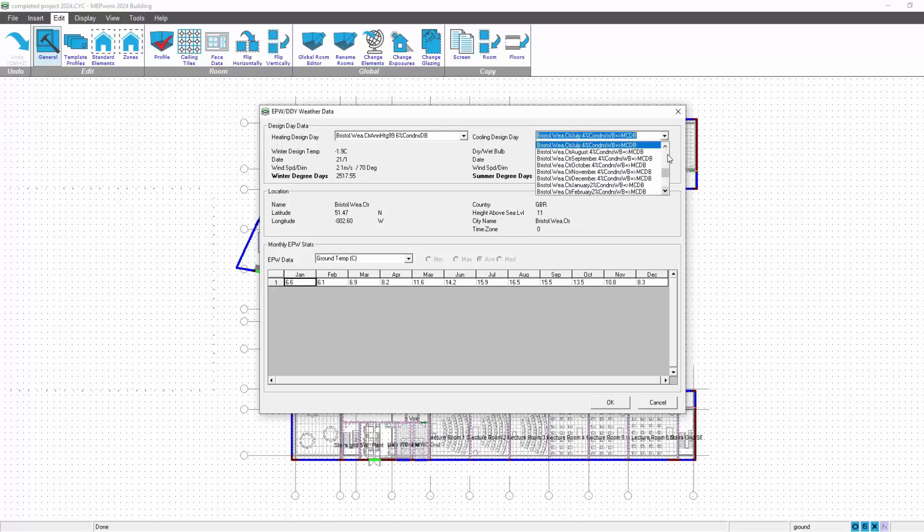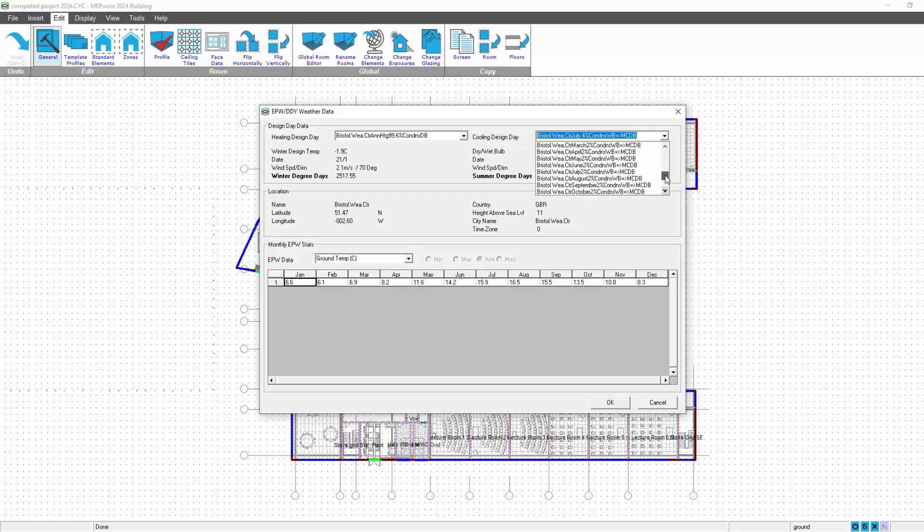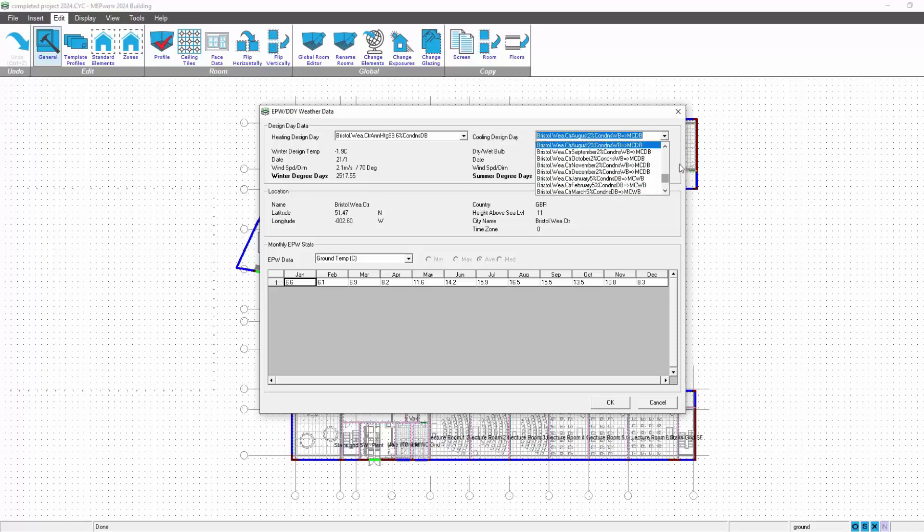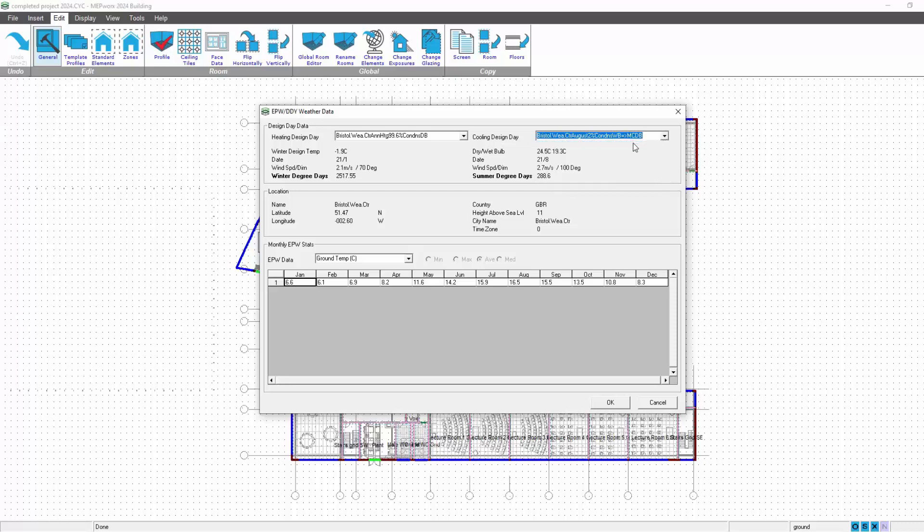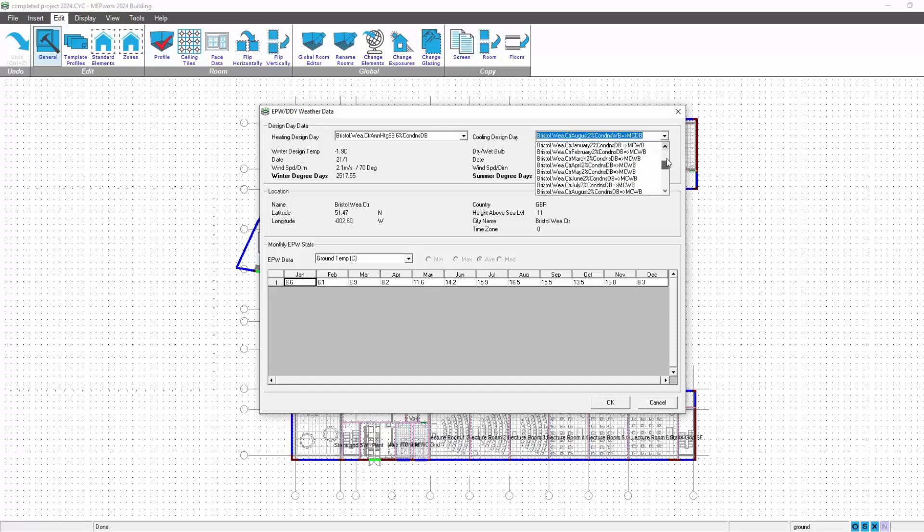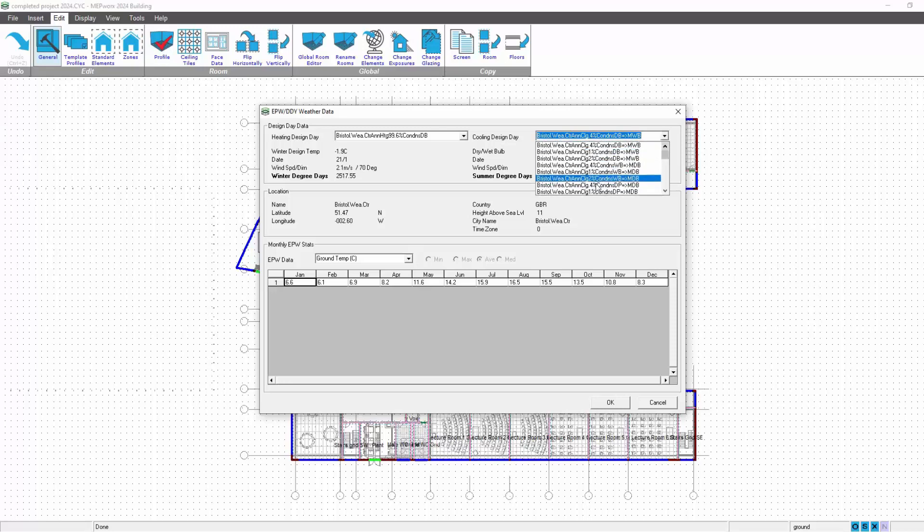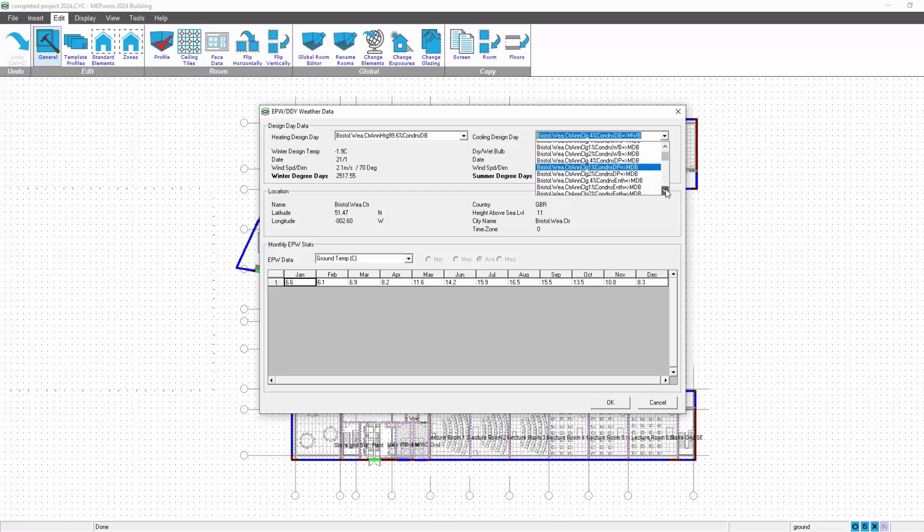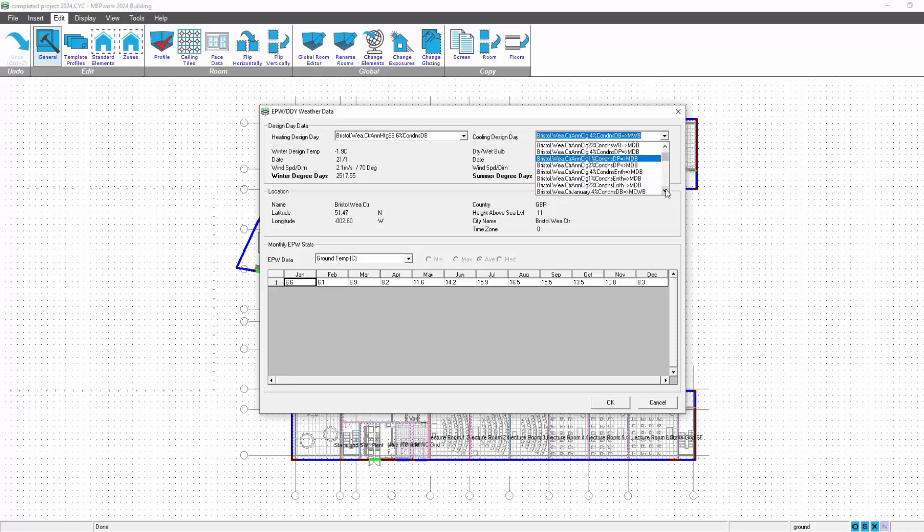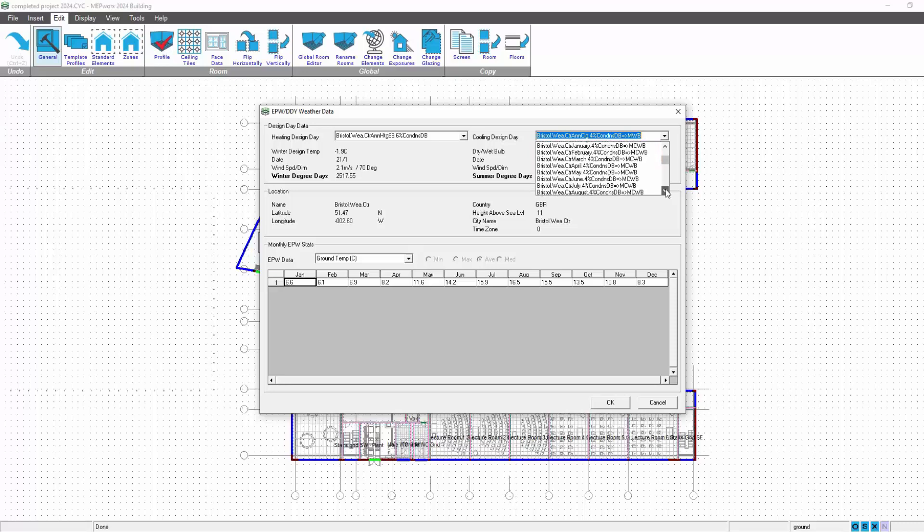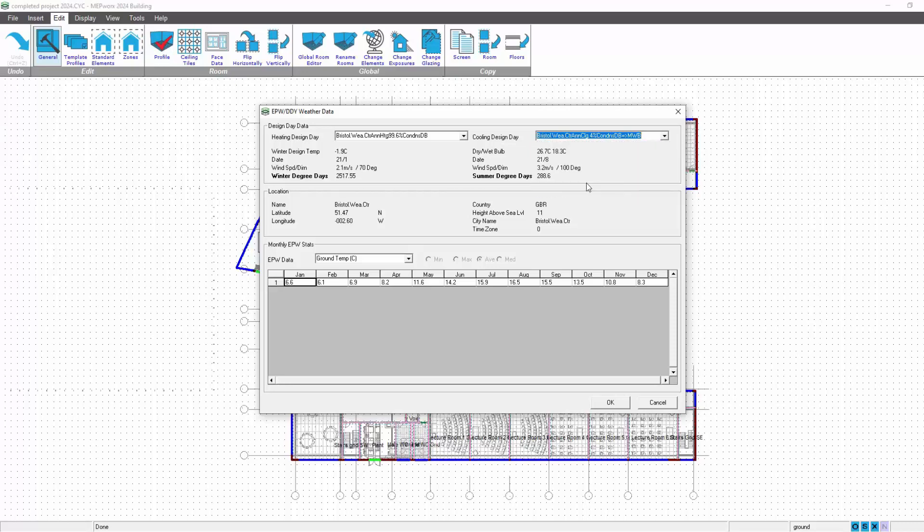So depending on the weather data set, you can get some slightly higher temperatures by picking other data sets. In this case, it does appear that the first one in the list is, on the face of it, one of the hottest locations, so I'll pick the first one. Takes me back to 26. There are higher temperatures available, so you do need to review this data. You could actually clear it from your database if you wanted to just include the maximum temperatures. All the information is in here. See, in August, 30.6, so you might want to use that.